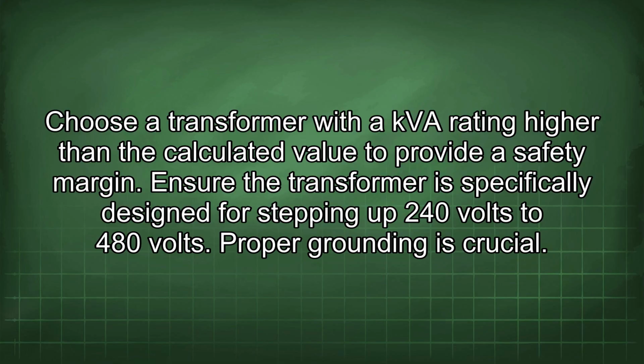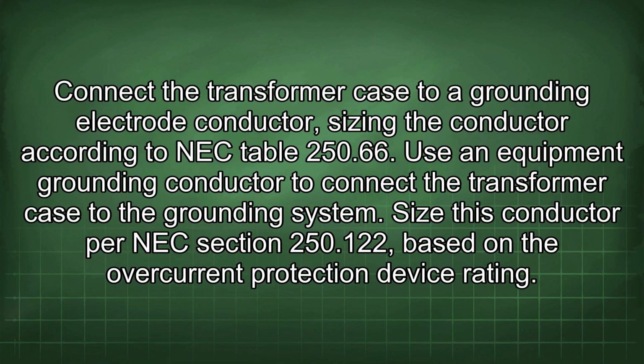Proper grounding is crucial. Connect the transformer case to a grounding electrode conductor, sizing the conductor according to NEC Table 250.66. Use an equipment grounding conductor to connect the transformer case to the grounding system. Size this conductor per NEC Section 250.122, based on the overcurrent protection device rating.